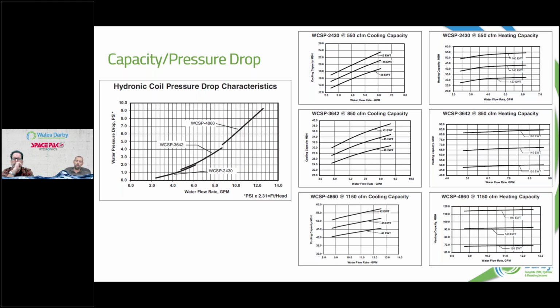We were able to adjust the one downstairs to what it needed to be, and we had an increase in GPM to the air handler up in the attic, and now we were getting the BTUs that we designed around. So since then, no complaints on the coldest days of the year. So that was pretty cool, and being able to understand that these charts are going to help us really understand, there is no more just throw it in, it's a 3-ton, it's 400, whatever, a ton per 400 square feet. There are no rules of thumb when designing these systems anymore.